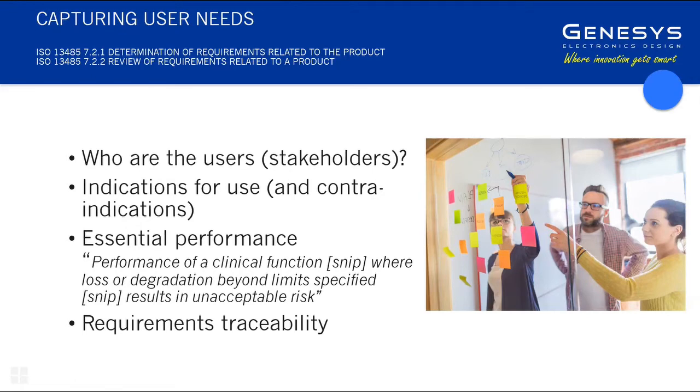There is a formal requirement that any artifact generated through the process of developing a medical product is traceable back to a user need. That includes right through to verification and validation. So if you're validating that your green light comes on when the power's on with a certain brightness and intensity, you'll have tests to verify that, and they will need to be traceable back to the user need.